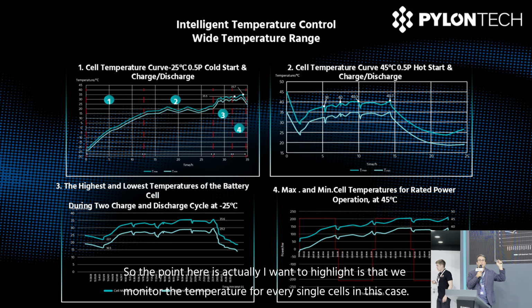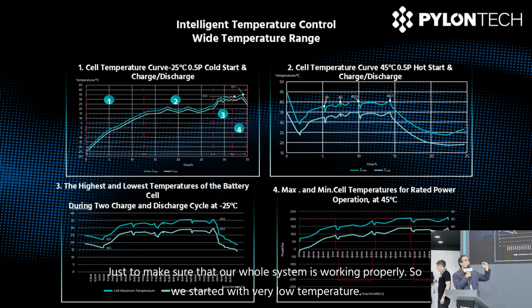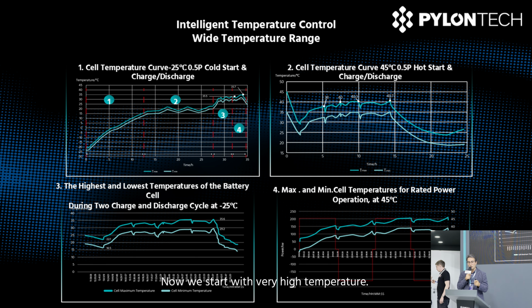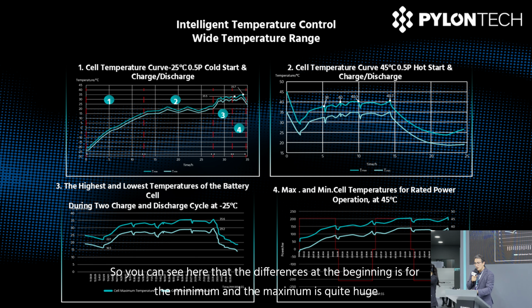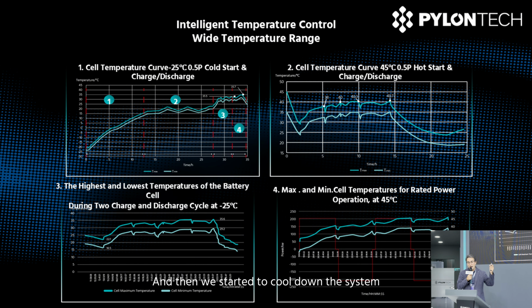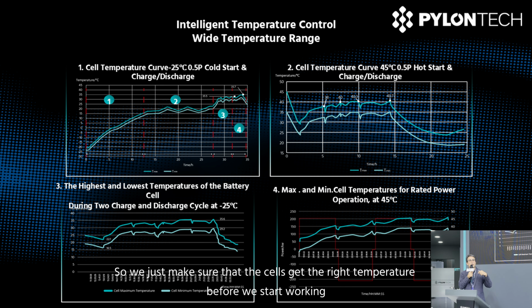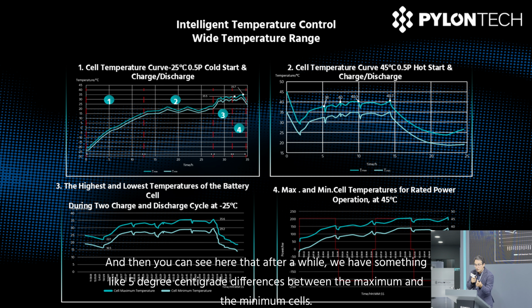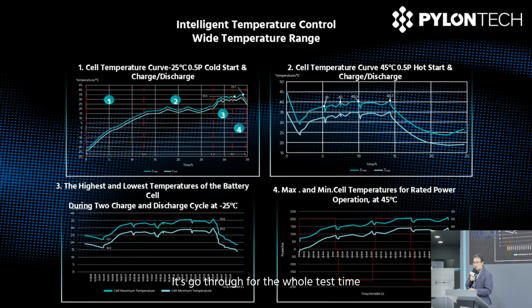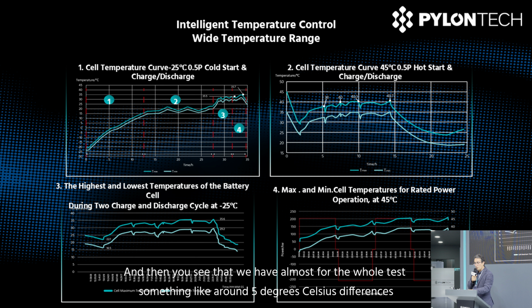The point I want to highlight is that we monitor the temperature of every single cell in this case, just to make sure that our whole system is working properly. So we started with very low temperature, now we start with very high temperature. You can see here that the difference at the beginning between the minimum and the maximum is quite huge. You have almost more than 10 degrees Celsius. And then we started to cool down the system. So the first phase is still not in operation mode. We just make sure that the cells get the right temperature before we start working. And then you can see here that after a while we have something like 5 degrees Celsius difference between the maximum and the minimum cells. It goes through the whole test time, and we have almost for the whole test something like around 5 degrees Celsius difference.